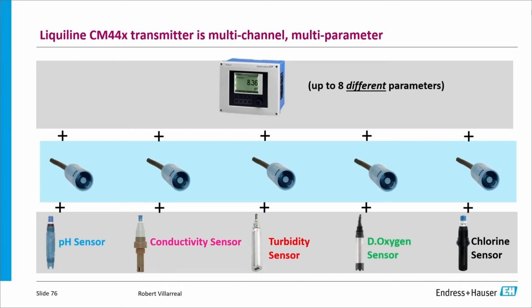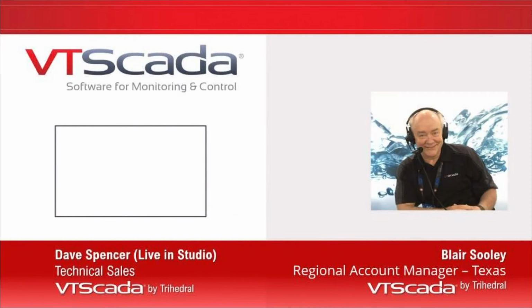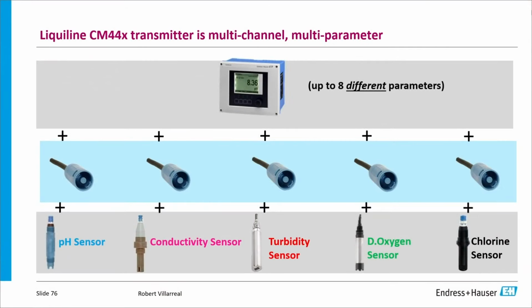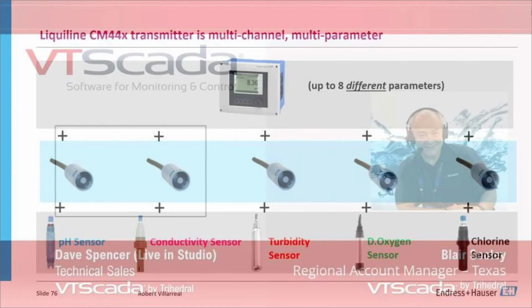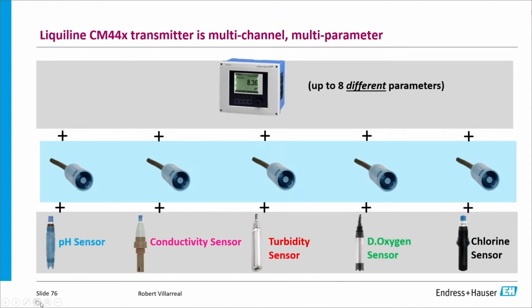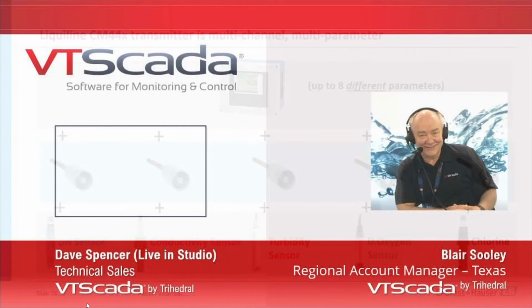Due to the sensor technology and using a digital protocol from the sensor to the transmitter, we can connect up to 8 different channels and export them all via an Ethernet protocol. Our transmitters are all Ethernet ready to simplify field wiring. Instead of doing a bunch of twisted pairs for 4-20s, we can do one Ethernet connection. We also still do the traditional 4-20 design as well, so we're trying to simplify this for the future.